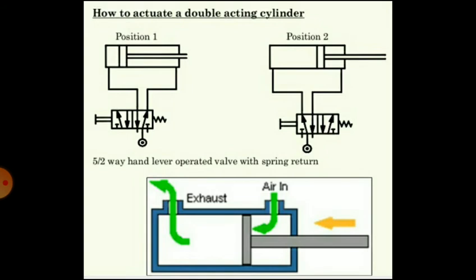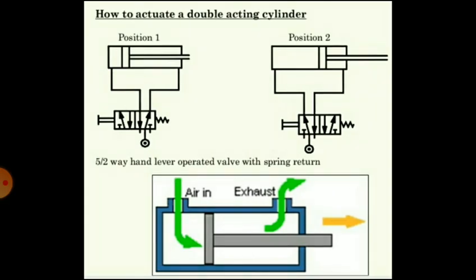To actuate a double acting cylinder: air enters through the piston rod end, forcing the piston backward — this is the retraction stroke — while compressed air at the piston end exits. When the valve is activated and its position changed, air enters through the piston end, forcing the piston forward, while compressed air at the piston rod side exhausts. This operation can also be followed in a circuit diagram.